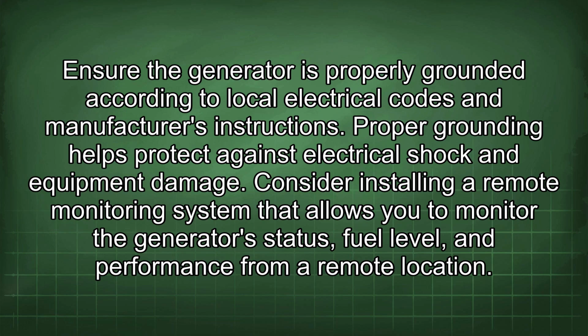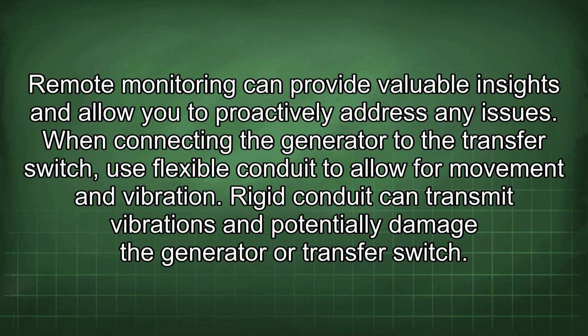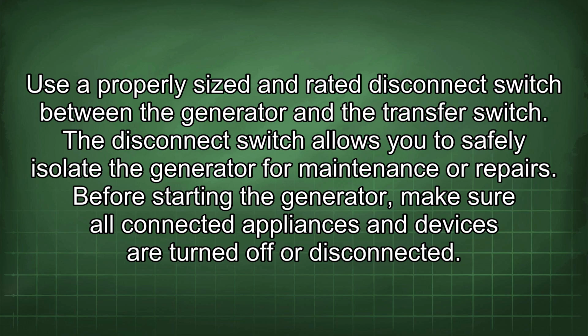Consider installing a remote monitoring system that allows you to monitor the generator's status, fuel level, and performance from a remote location. Remote monitoring can provide valuable insights and allow you to proactively address any issues. When connecting the generator to the transfer switch, use flexible conduit to allow for movement and vibration. Rigid conduit can transmit vibrations and potentially damage the generator or transfer switch. Use a properly sized and rated disconnect switch between the generator and the transfer switch.